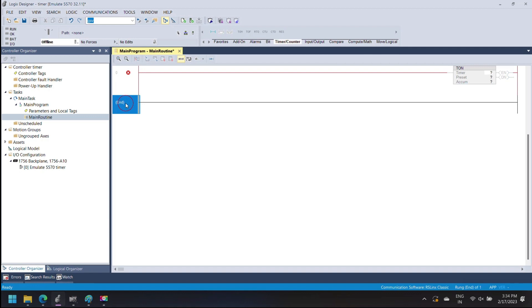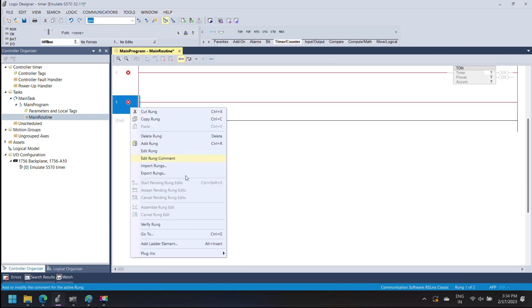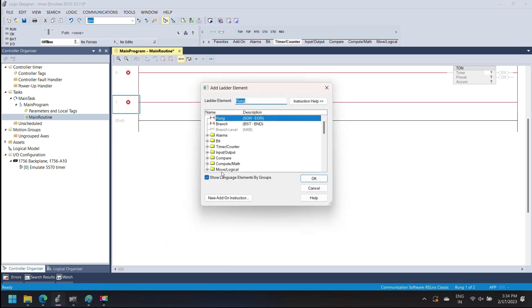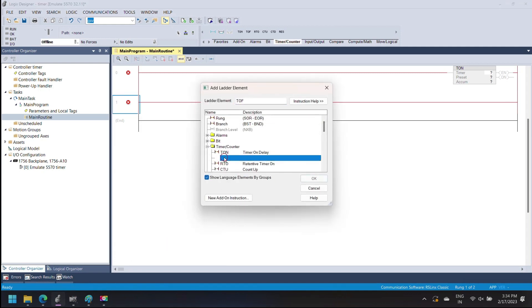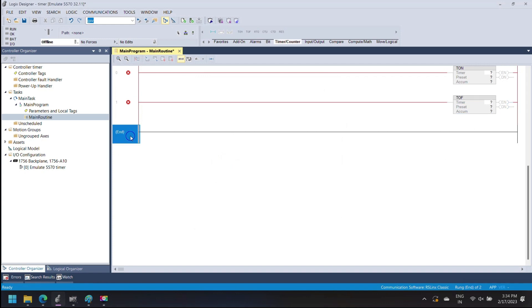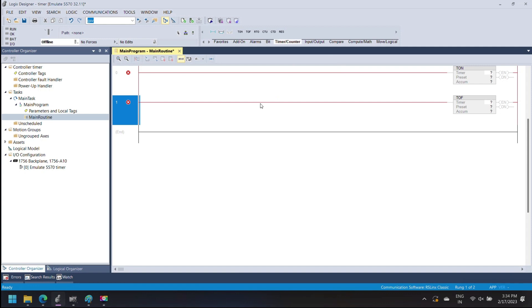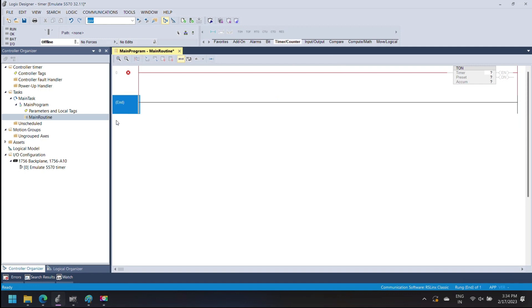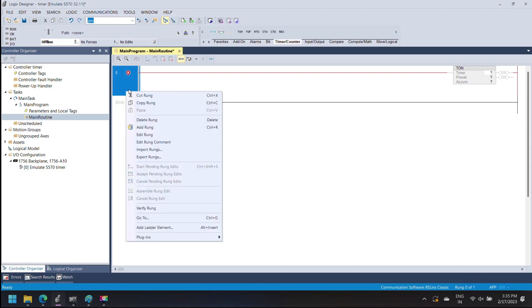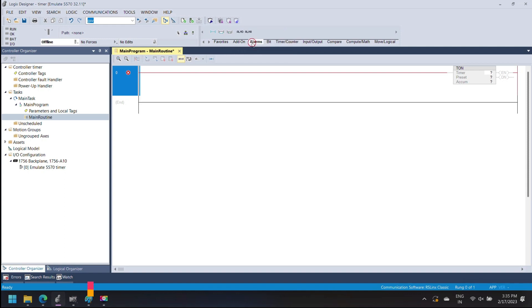In RSLogix 5000 you can add timer instructions from the language element toolbar. The language element toolbar is a tab toolbar which shows the instruction set available for your language. Select the timer/counter category and drag your timer and counter to the rung. Or you can add your instruction directly by right-clicking on the rung, selecting add ladder element, and browsing timer/counter to add the timer.